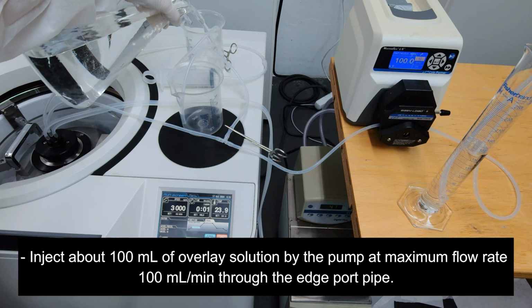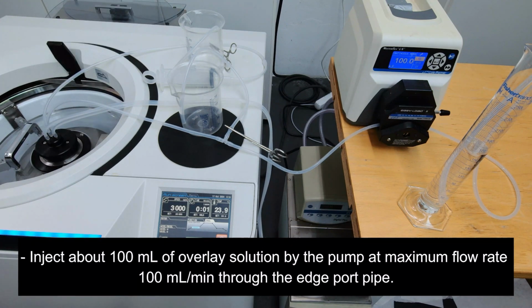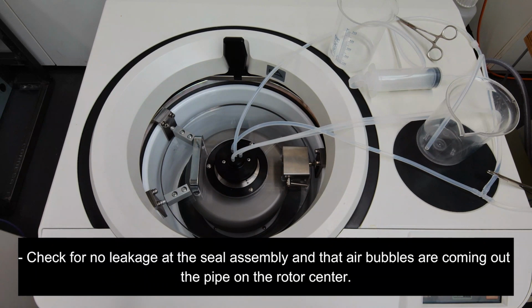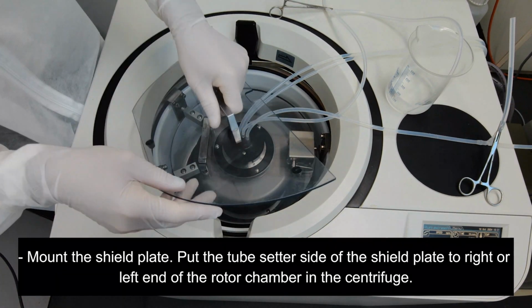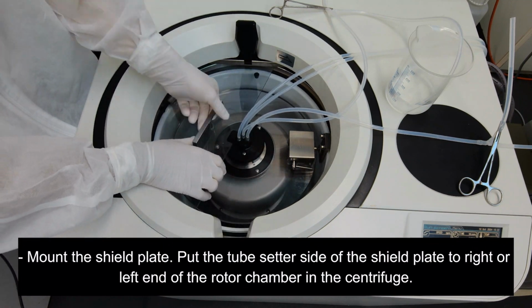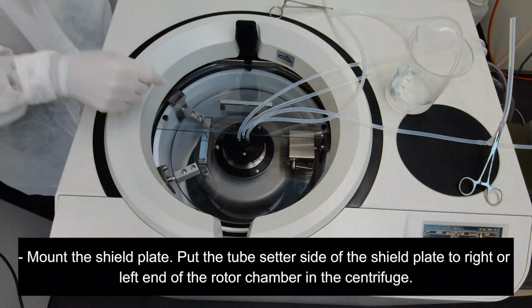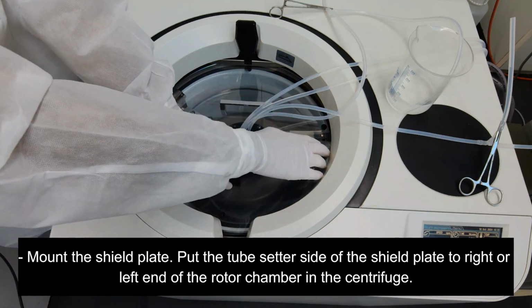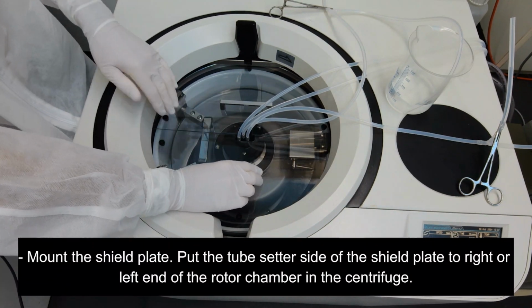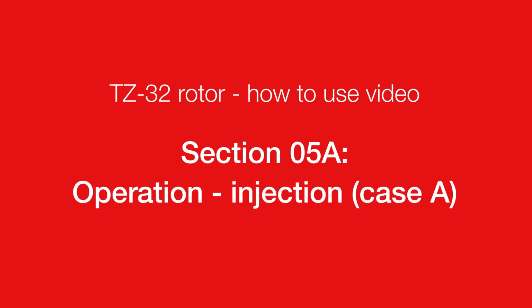Inject about 100 ml of overlay solution by the pump at maximum flow rate 100 ml per minute through the edge port pipe. Check for no leakage at the seal assembly and that air bubbles are coming out the pipe on the rotor center. Mount the shield plate. Put the tube setter side of the shield plate to the right or left end of the rotor chamber in the centrifuge.